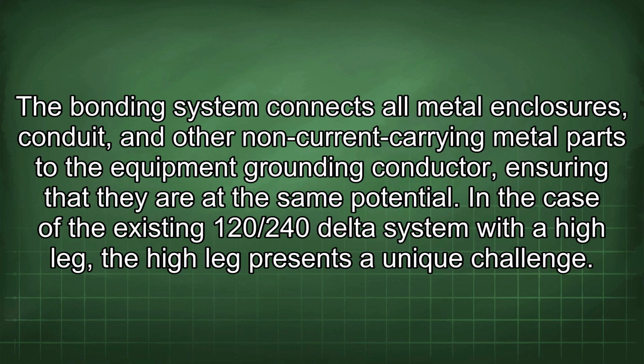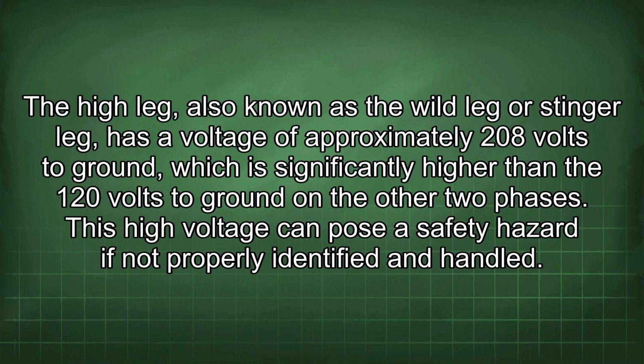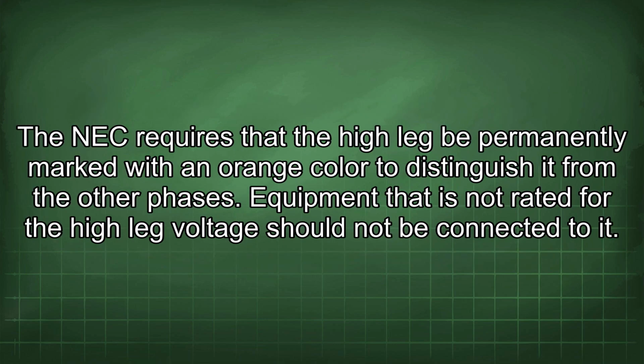In the case of the existing 120/240 delta system, the high leg presents a unique challenge. The high leg, also known as the wild leg or stinger leg, has a voltage of approximately 208 volts to ground, which is significantly higher than the 120 volts to ground on the other two phases. This high voltage can pose a safety hazard if not properly identified and handled. The NEC requires that the high leg be permanently marked with an orange color to distinguish it from the other phases. Equipment that is not rated for the high leg voltage should not be connected to it.